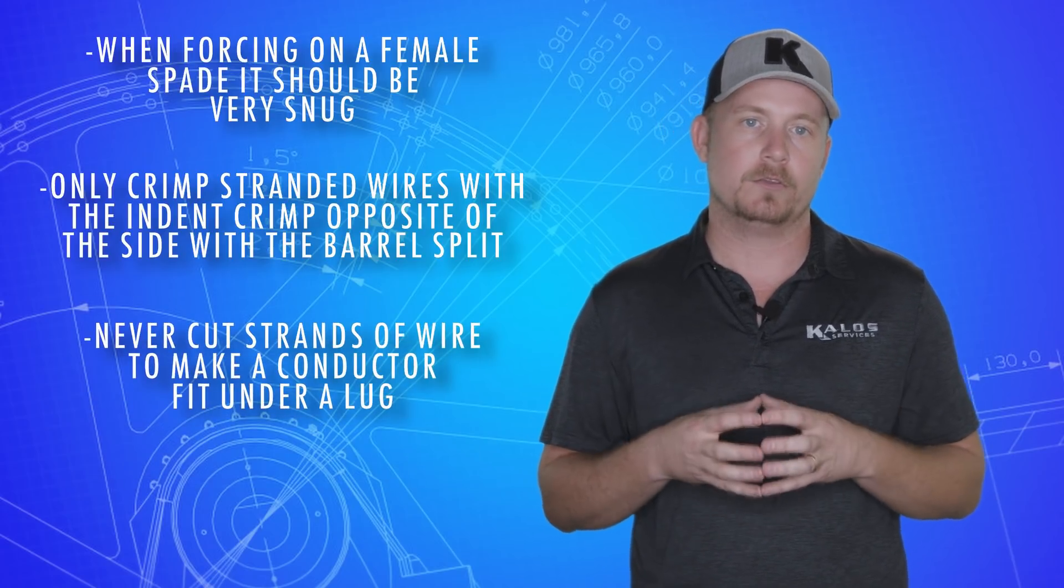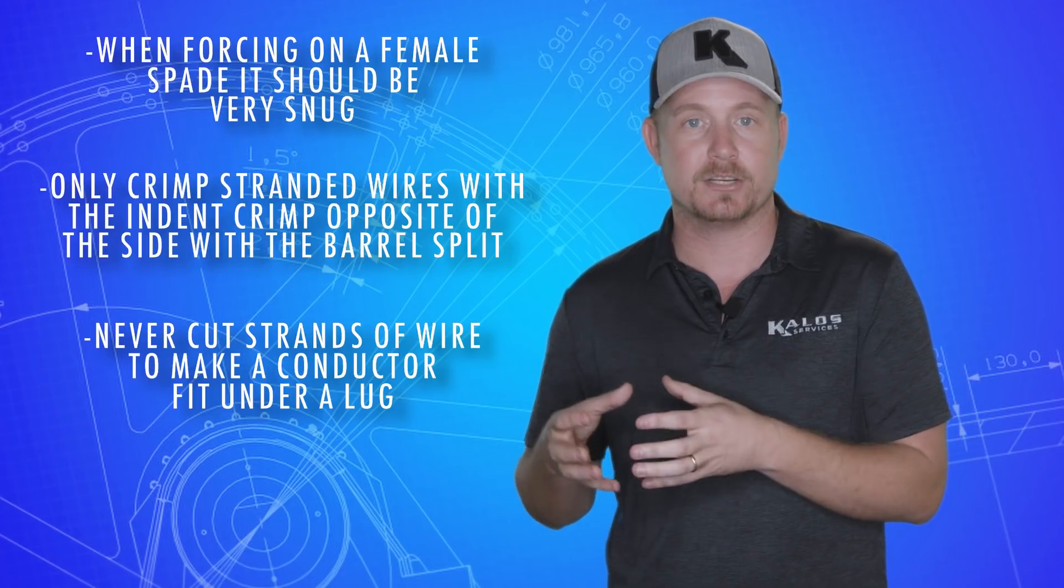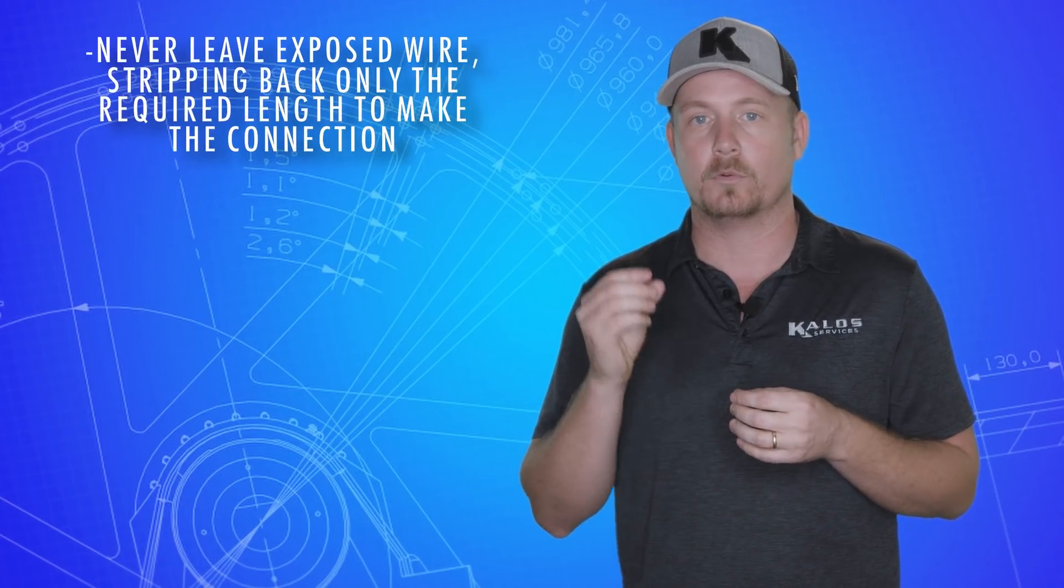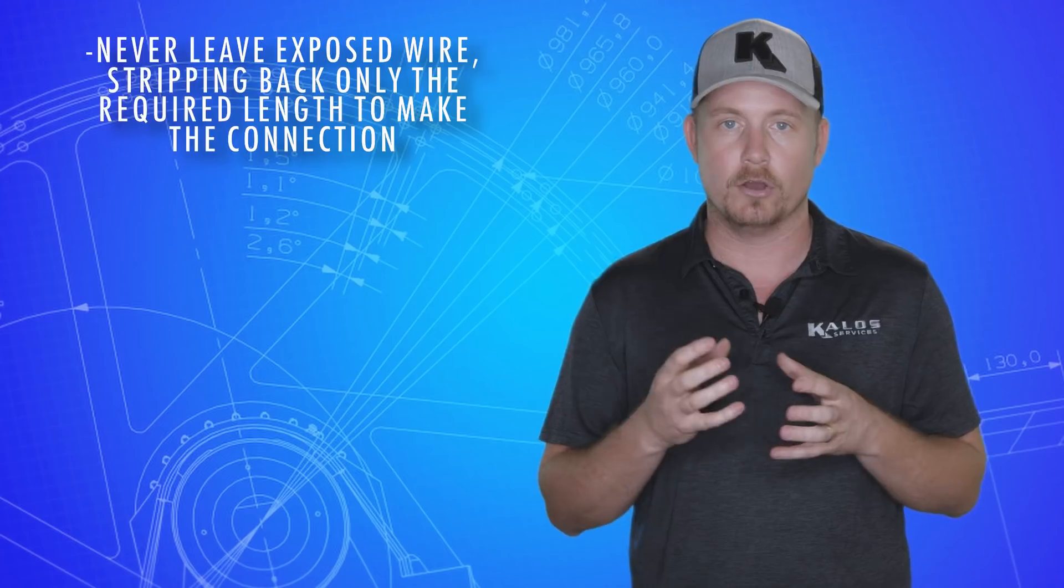Never cut strands of wire to make a conductor fit under a lug. Use the proper connector termination type for the conductor, and it has to be the right size. Never leave exposed wire. Strip back insulation only to the length required to make the connection and no more.